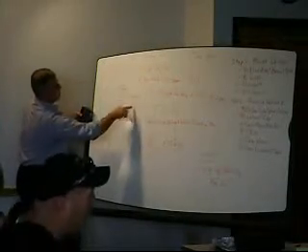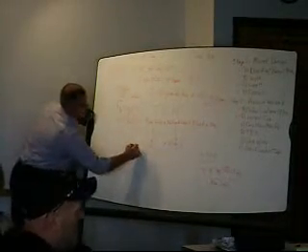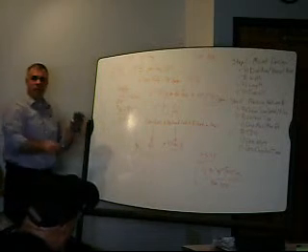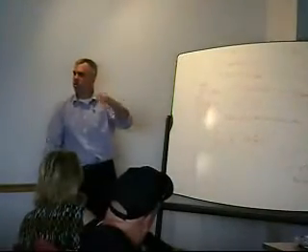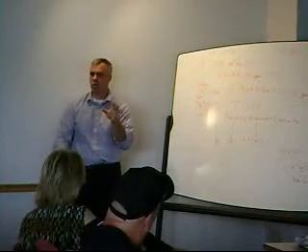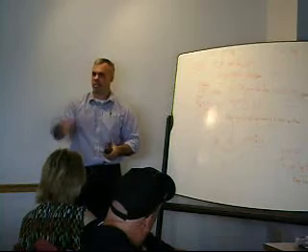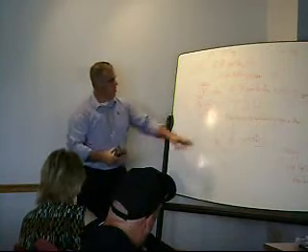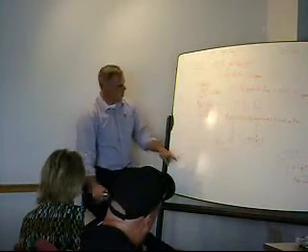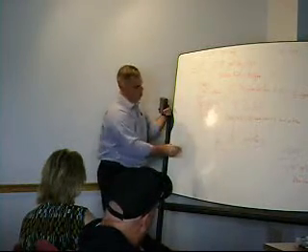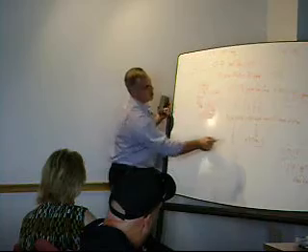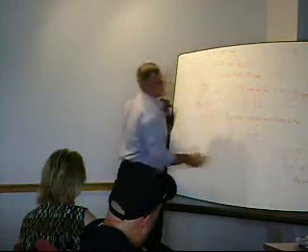The head that we recommend here is 3.5 feet at the end. What that means is when I take a squirt tube and stick it at the end of that mound and tie it in there, that thing should shoot up in that squirt tube 3.5 feet. You know what a squirt tube is? You're checking the head pressure at the end of the mound. 3.5 feet is where that should be. When it's delivered to the center of the mound is what we really want to know. We want to know what it needs to be here.